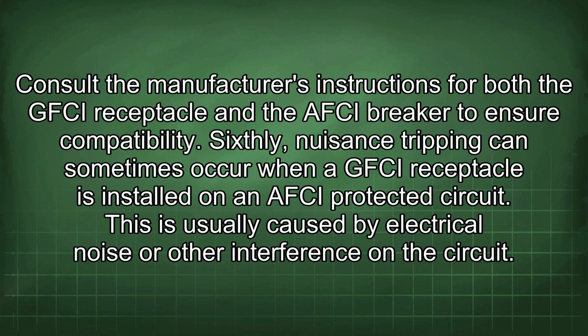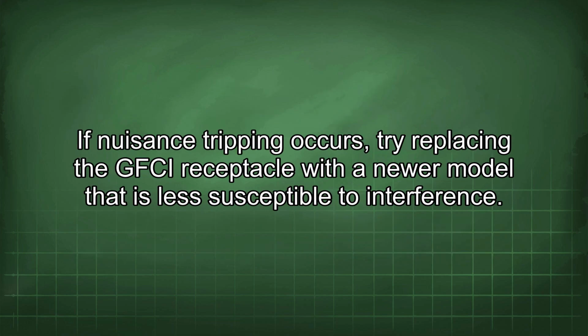Sixthly, nuisance tripping can sometimes occur when a GFCI receptacle is installed on an AFCI protected circuit. This is usually caused by electrical noise or other interference on the circuit. If nuisance tripping occurs, try replacing the GFCI receptacle with a newer model that is less susceptible to interference.